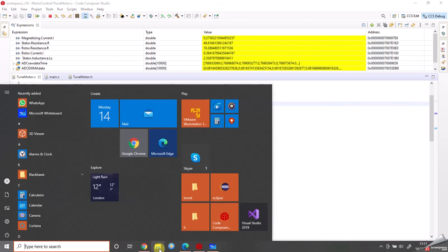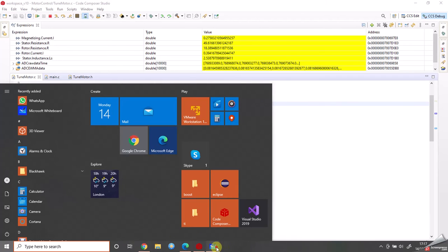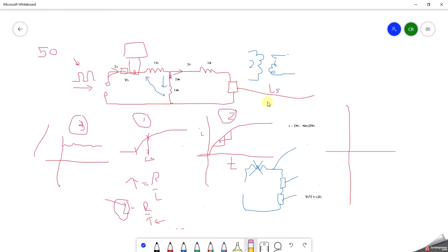So if we come back to my little squiggly drawing over here, I must admit it's not the best drawing, but anyway. So now that I can get this guy over here, the rotor resistance, okay, we're sort of on our way. So more or less we have everything. There are some leaps of faith here, but we can glean a lot of the data off the nameplate, so we can make references to NEMA standards. So for the ratio of this leakage over here compared to this leakage, we can make reference to that.